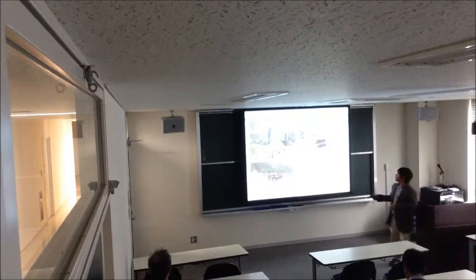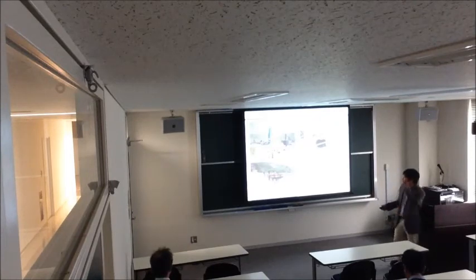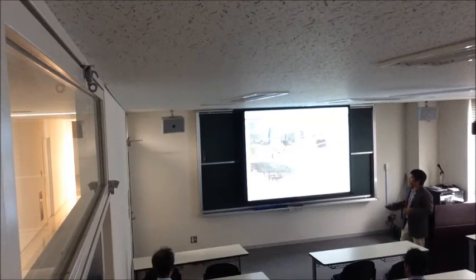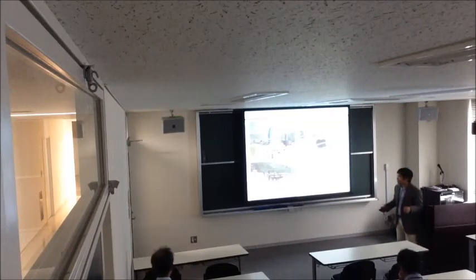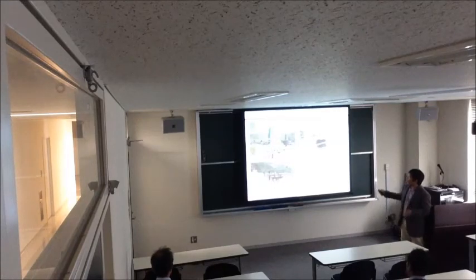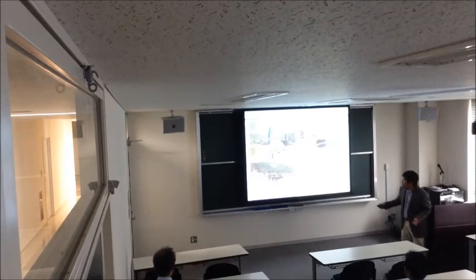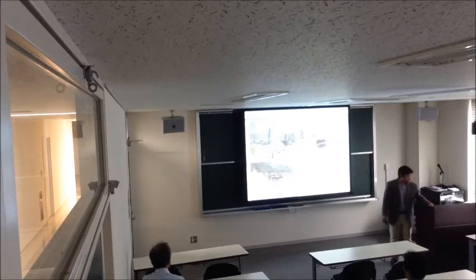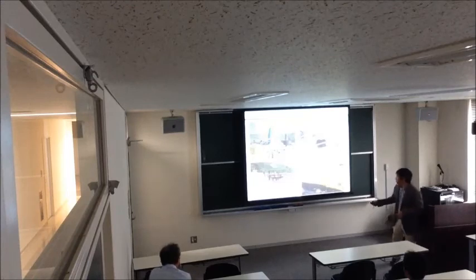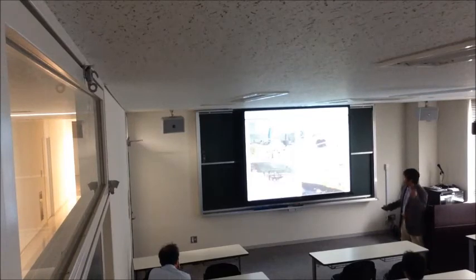Then after this one, this is the ponds. So brine will flow to the ponds, and this pond will hold the brine for several hours before it is injected into the reservoir. This is the pump, and this is the pump pipe. The pump sucks the brine and sends it to the injection well here. But the problem is this one. This is the pipe here. You can see that the pipe will sometimes break because there is scaling there.